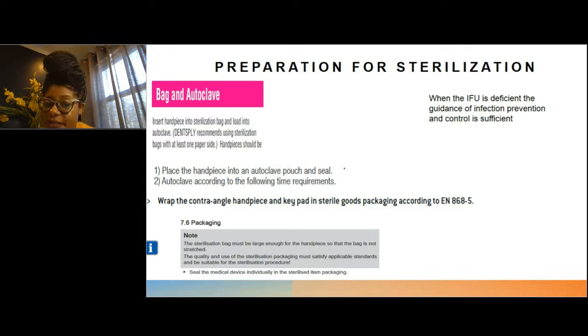So, preparation for sterilization. One of the things I wanted to point out is that if the IFU is deficient in guidance on infection prevention and control, your guidance for infection prevention and control is sufficient. If you look at these excerpts, they just say bag and autoclave. Insert the handpiece in a sterilization bag and load into an autoclave. Wrap the contra-angle handpiece and keypad in sterile bag packaging. The IFU simply says that after inspection, you place the handpiece within a sterilization bag. But what it does not say is that you need to have a chemical indicator within it.